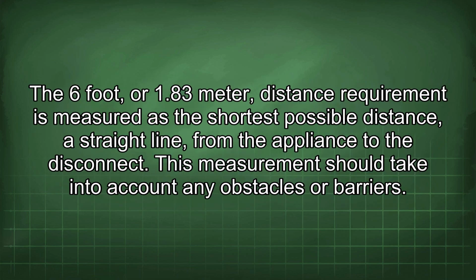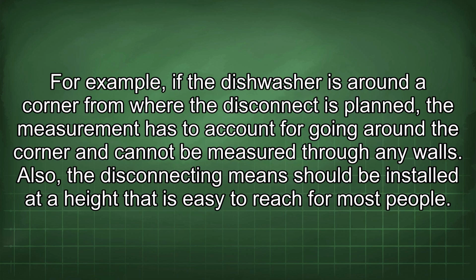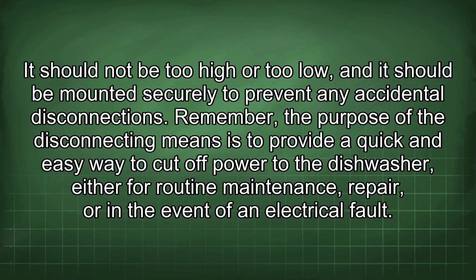The 6 foot, or 1.83 meter, distance requirement is measured as the shortest possible distance, a straight line, from the appliance to the disconnect. This measurement should take into account any obstacles or barriers. For example, if the dishwasher is around a corner from where the disconnect is planned, the measurement has to account for going around the corner and cannot be measured through any walls. Also, the disconnecting means should be installed at a height that is easy to reach for most people. It should not be too high or too low, and it should be mounted securely to prevent any accidental disconnections.